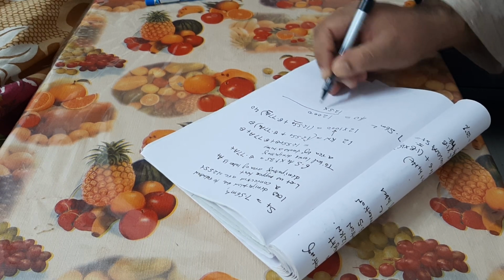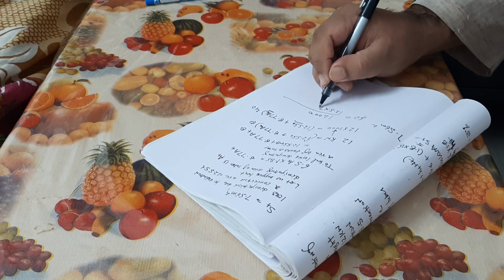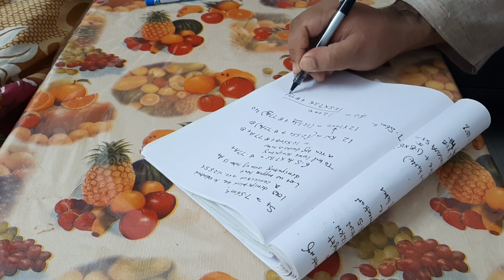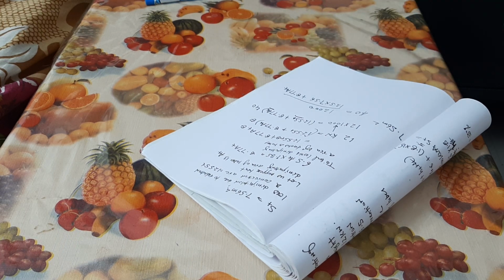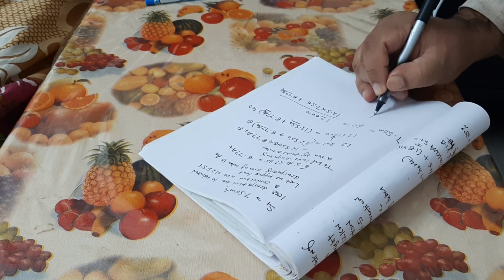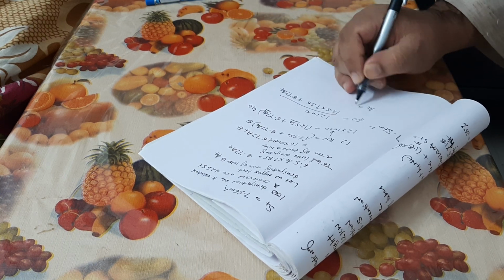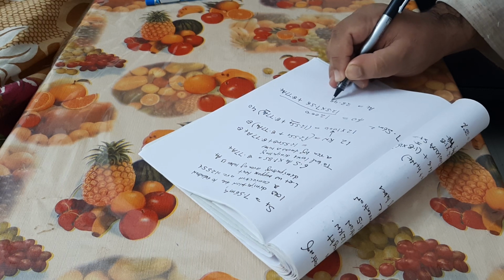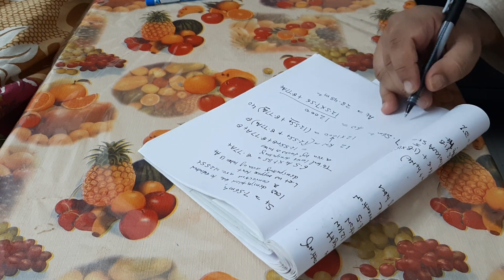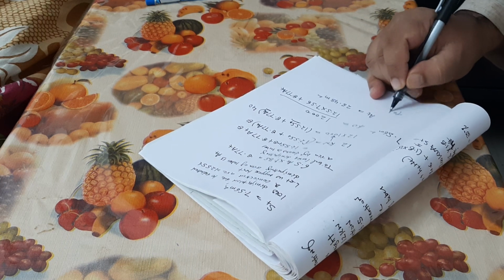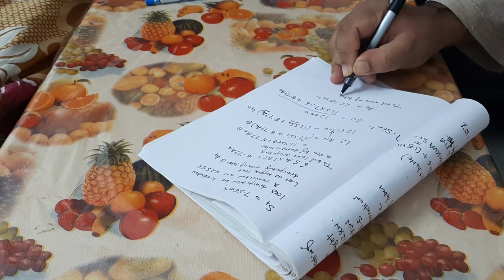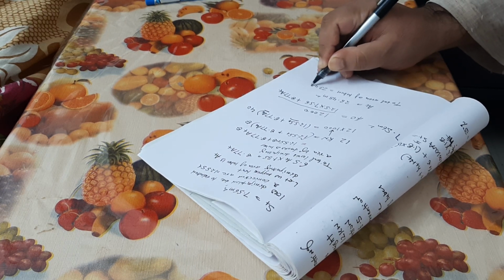12.5, instead of St we directly take the value 7.56, and plus 8.7780. So now obviously we have the value, we cross multiply and we get the value of At. So the value of At would be around 23.43 meter square. So the total area of the tubes happens to be 23.43 meter square.